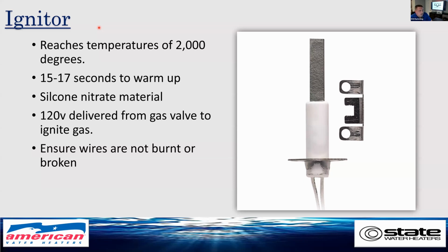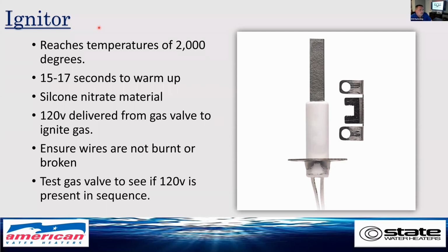Troubleshooting-wise, you need to ensure that you have no burnt or broken wires leading to it. And you can always test the gas valve to see if 120 volts is present in the sequence of operation when it would call for that, which would be right after the pressure switch closes. Good part to know is the ceramic over time will become cracked or damaged, which then can cause your igniter to fail.